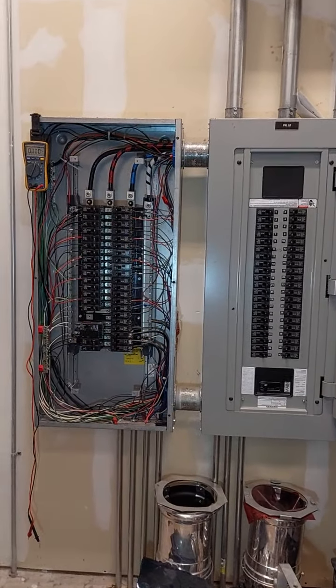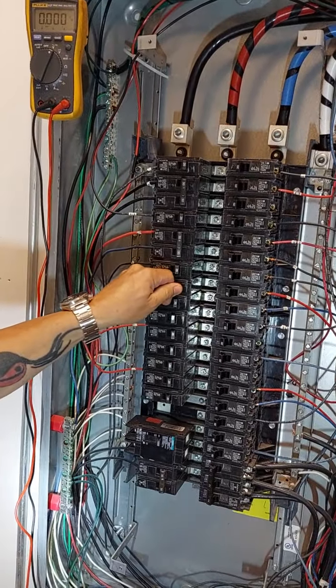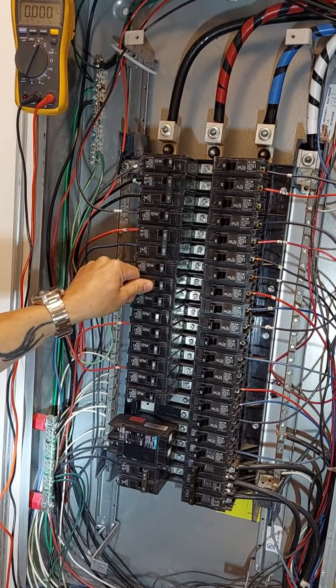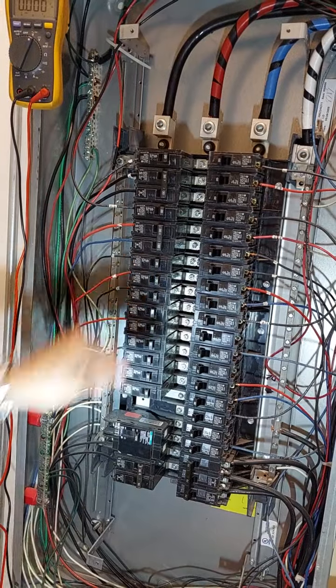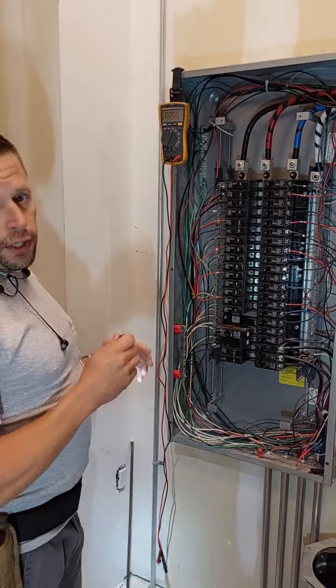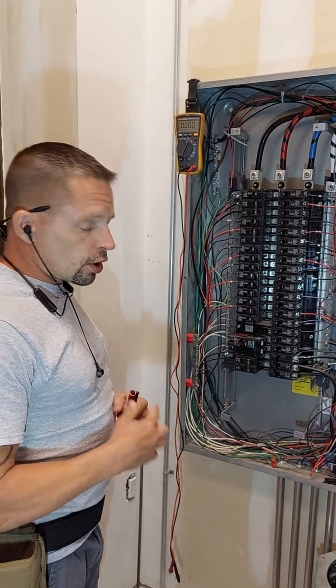Now we're going to rack our breaker 57. And you see we rack it, the arc flash is now gone. The breaker is tight and secured. We will no longer get any loss of AC power down to the power supplies directly below us.